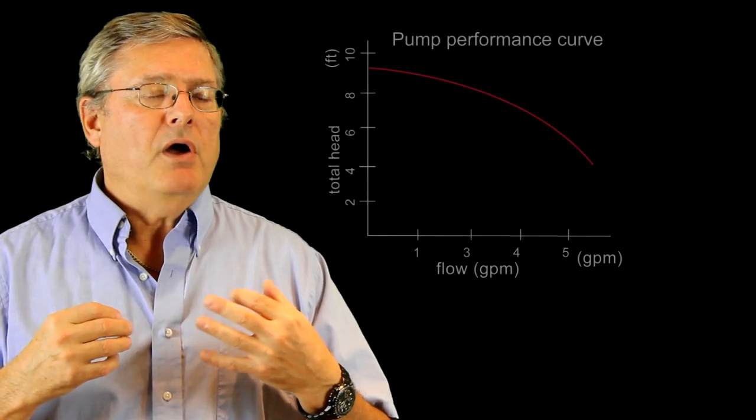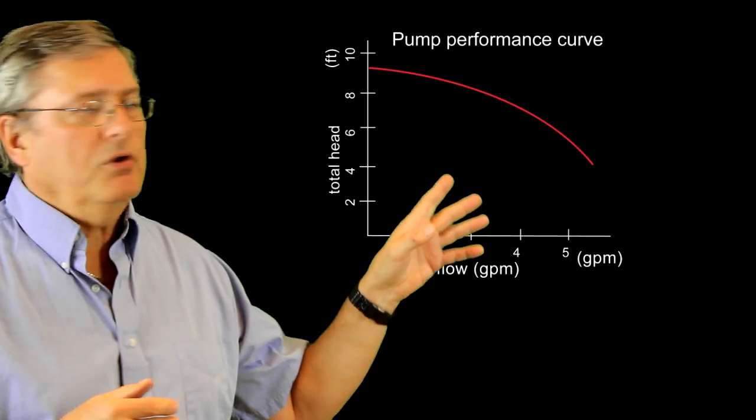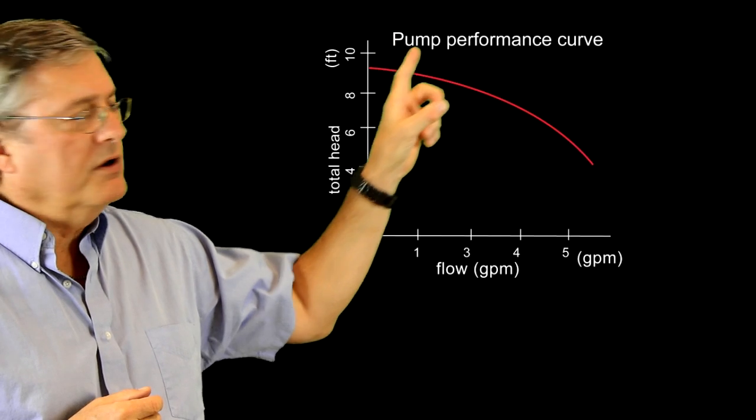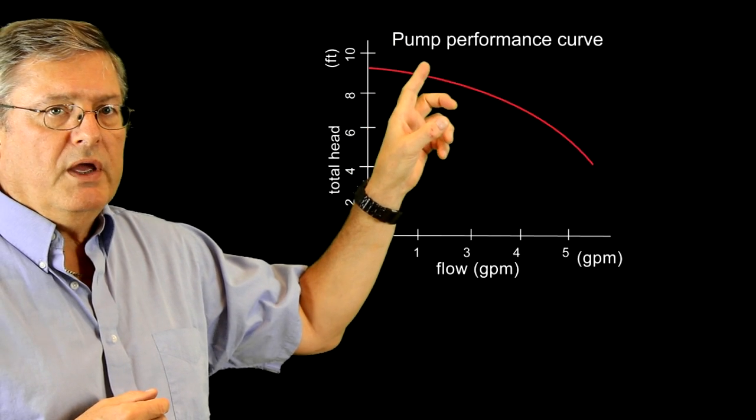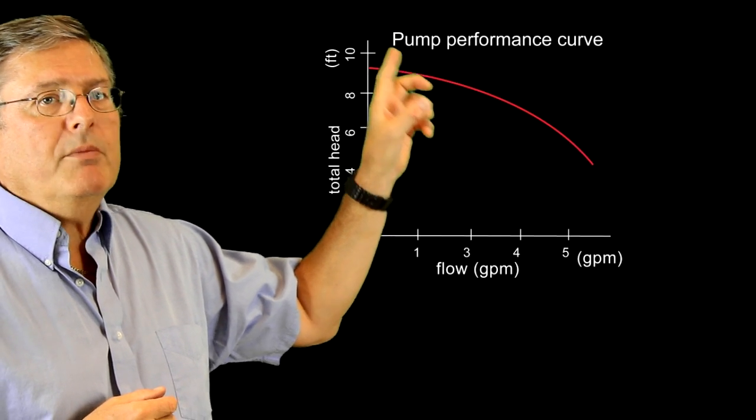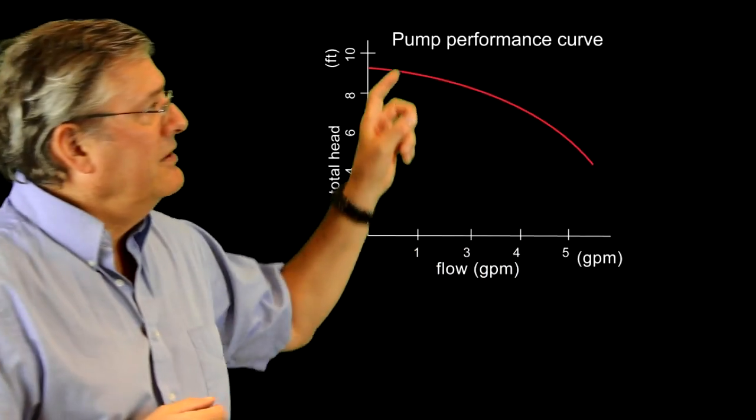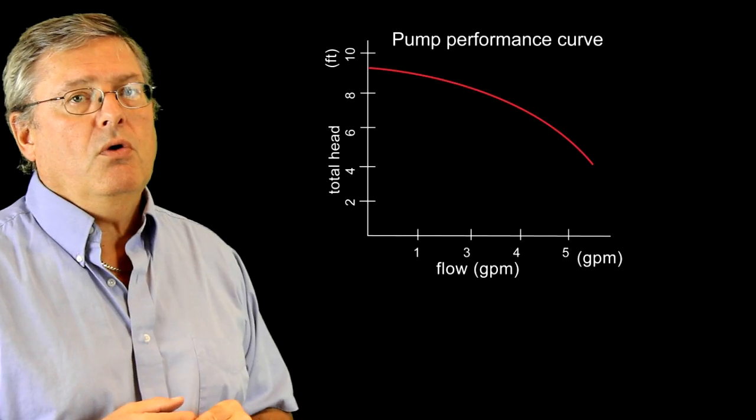So the thing about centrifugal pumps is they all have a very similar characteristic curve of head and flow. So you can see at this point here, at the low flow end or zero flow, we have the maximum head, and that's also called shutoff head. And at the other end we have the maximum flow and the lowest head.